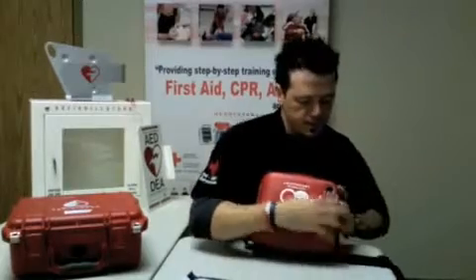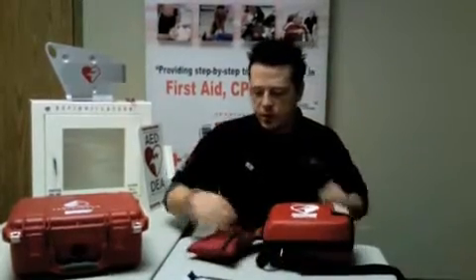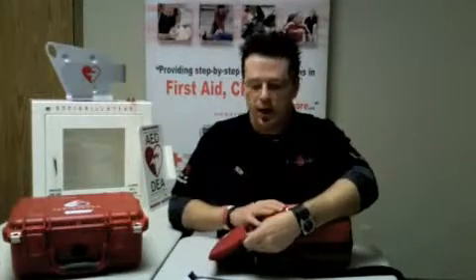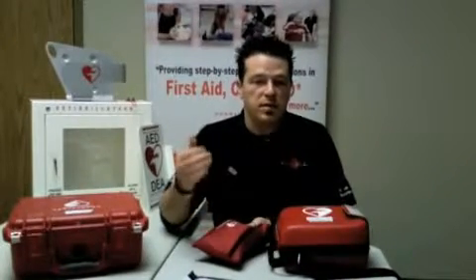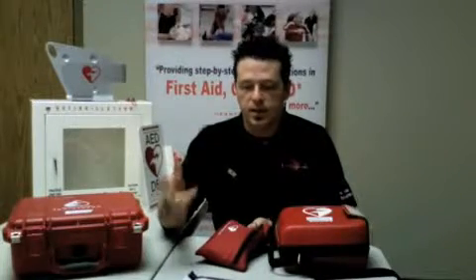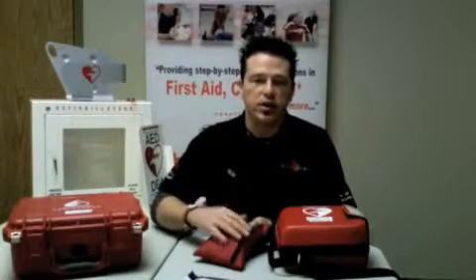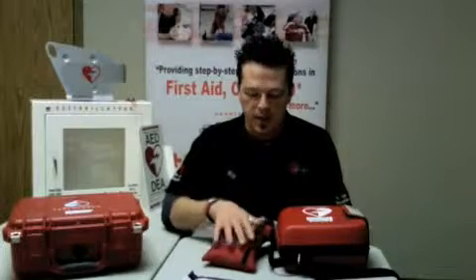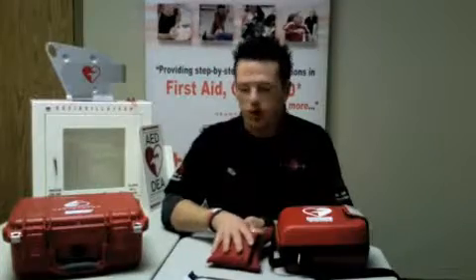Closing up the case. The last thing to assess would be to make sure that the fast response kit, which is a little bag that should be attached to the defibrillator case, is current. Now, there should be 5 things: a pair of scissors, a pair of gloves, a pocket mask, a razor, as well as a paper towel to make sure that if the electrodes are being put on the person's chest, it can actually be wiped. As long as those 5 things are in the fast response kit and they look to be in good working order, that's all that needs to be done with the fast response kit.